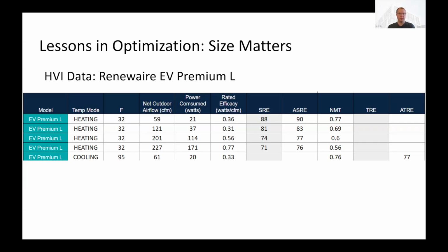As airflow increases, power consumption goes up, right? The fans are working harder. They're trying to jam more and more airflow through the machine or through the heat exchanger core, and so the fan power is going to go up. The other thing that's happening is the air is moving a lot faster. If we go from 59 to 121 CFM, we've doubled the CFM, so we're doubling the airspeed through the core. And what you can see in terms of the apparent sensible recovery efficiency, or ASRE, is a reduction from 90% down to 83% because the air is moving faster through the core.